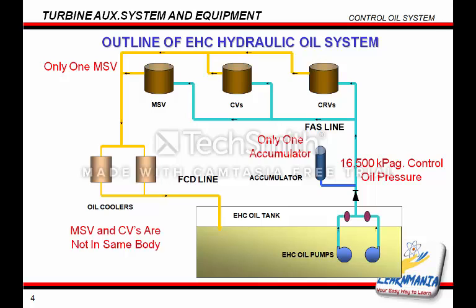The EHC oil system comprises two pumps, an oil tank, two oil coolers, and one accumulator. It supplies oil to the CVs, MSVs, and CRVs via a filter. The small size of the hydraulic cylinders, made possible by the high pressure of the oil, results in high system control. Fire-resistant oil is used in this system due to the high fire danger in the event of a high-pressure oil leakage. Control oil is maintained at 2,400 psi for new combination type MSV and CV valves, and at lower pressures for directly connected MSV-CV valves.